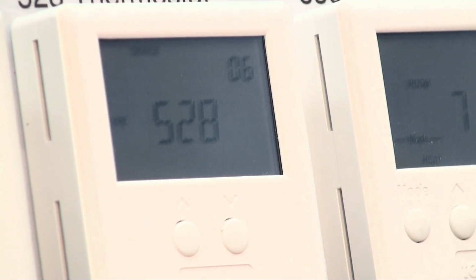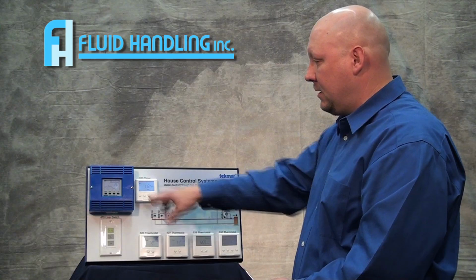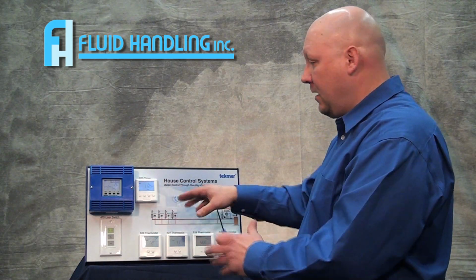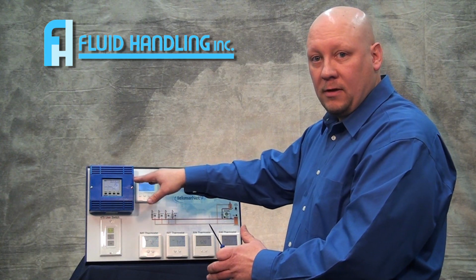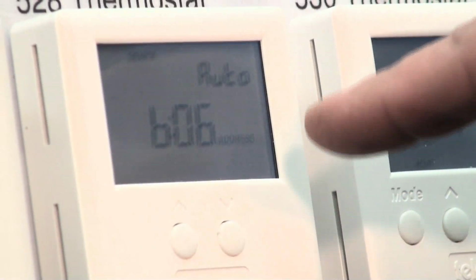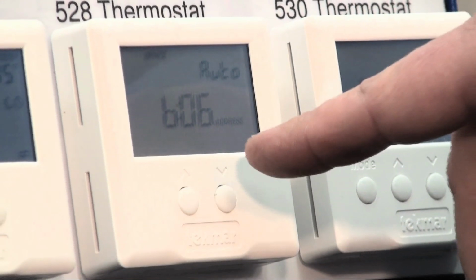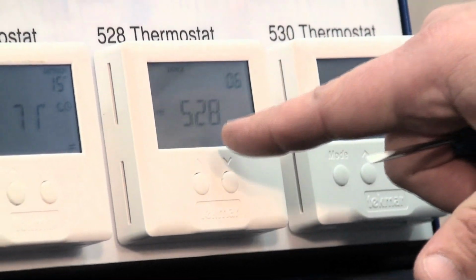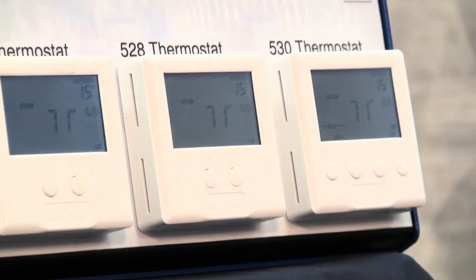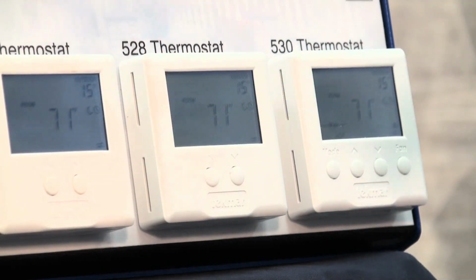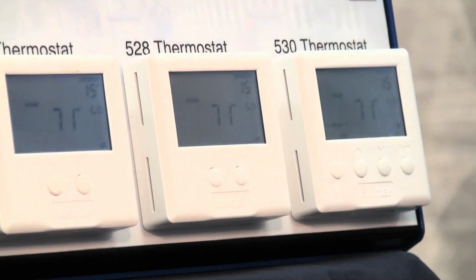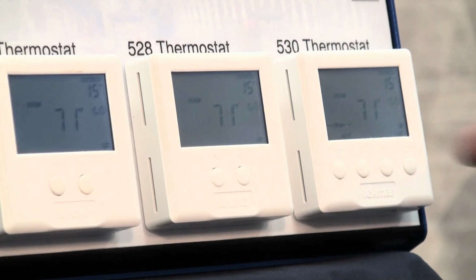And now we're back to, this is device number 06. So up here on my bus, if it showed me that device lost as 606, this is my thermostat that went missing. And then it's showing the current, it's a 528 and it's 06. And you saw it flash where it was showing auto. It was just auto addressing itself to the control, and it stayed on 06.